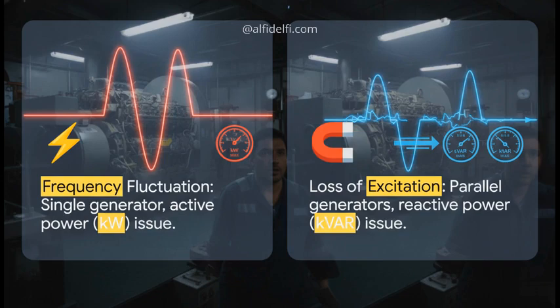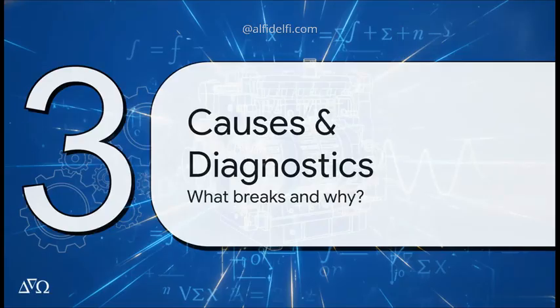On the flip side, loss of excitation is a parallel operation fault. Picture this: you've got 2 generators already synchronized, happily sharing the load. Then, out of nowhere, one loses its magnetic field and starts drawing massive reactive power, or kVAR, from its healthy partner. The frequency? Well, it might actually stay stable at first, but your voltage and currents? Absolute chaos.